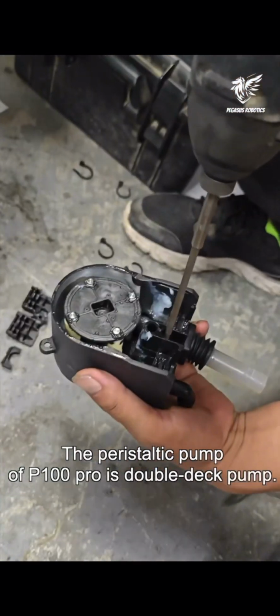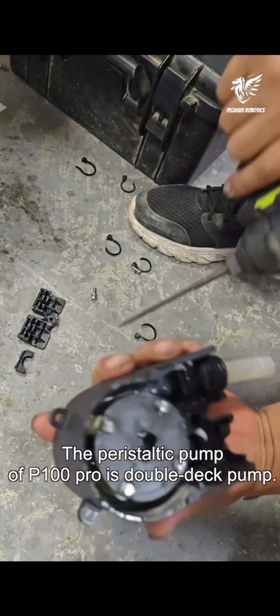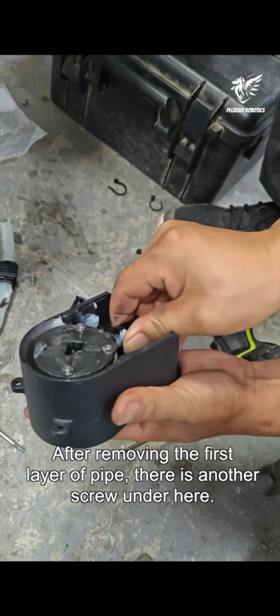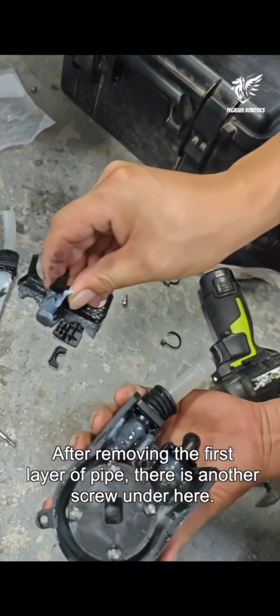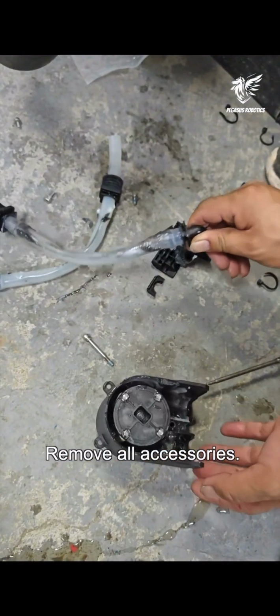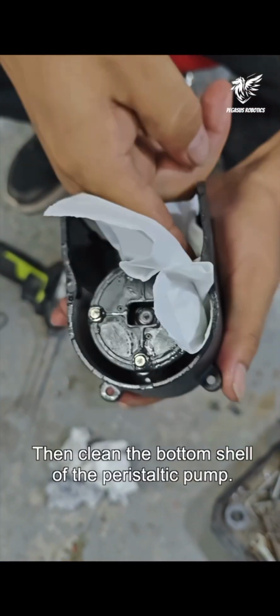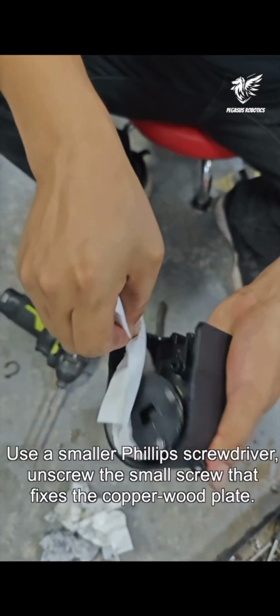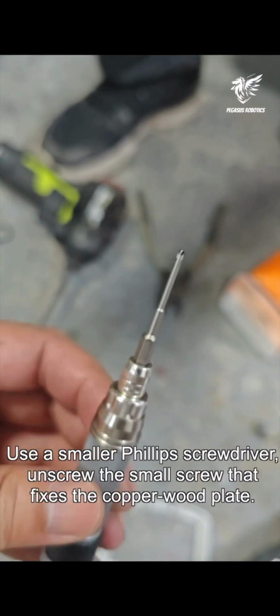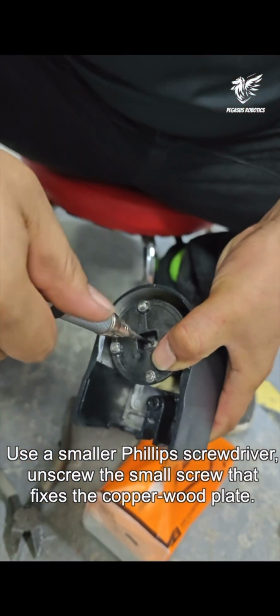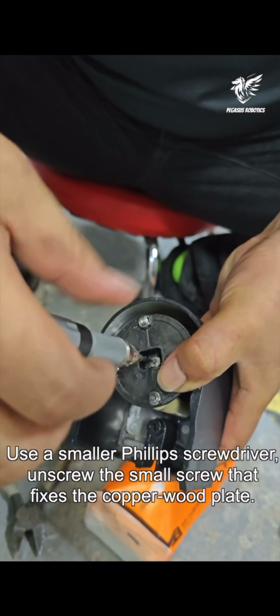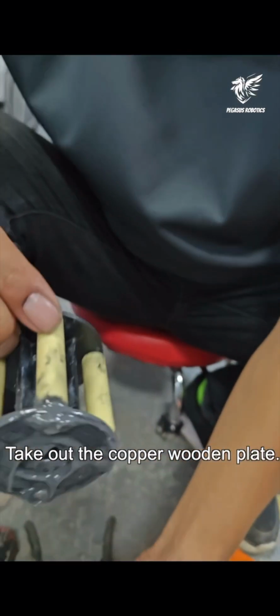The peristaltic pump of P100 Pro is a double-deck pump. After removing the first layer of pipe, there is another screw under here. Remove all accessories. Then clean the bottom shell of the peristaltic pump. Use a smaller Phillips screwdriver. Unscrew the small screw that fixes the copper wood plate. Take out the copper wooden plate.